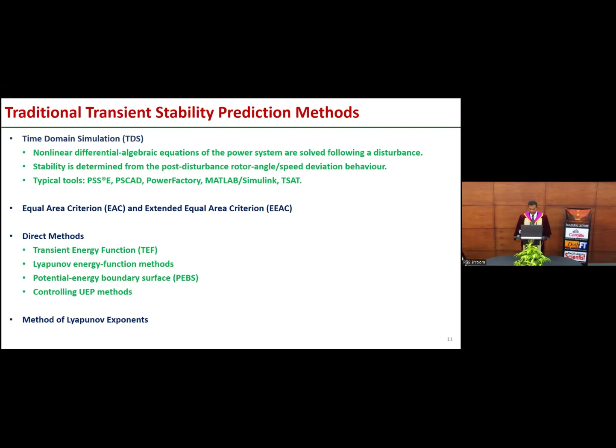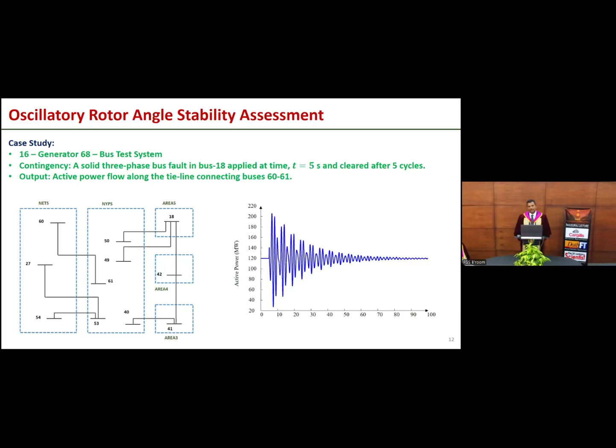Then we come to the problem of oscillatory stability, whether the system oscillations have adequate damping. That's the main issue in oscillatory stability assessment. We need to determine what oscillations are present in the network and whether they have enough damping. This is a case study for a 16-generator system where the power flow through one of the tie lines varies as shown in the graph. We have to process it and identify whether the system has adequate damping or not.